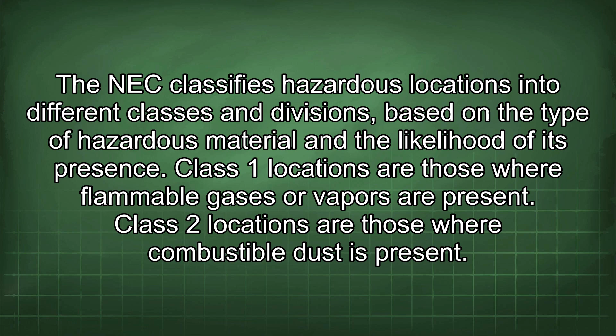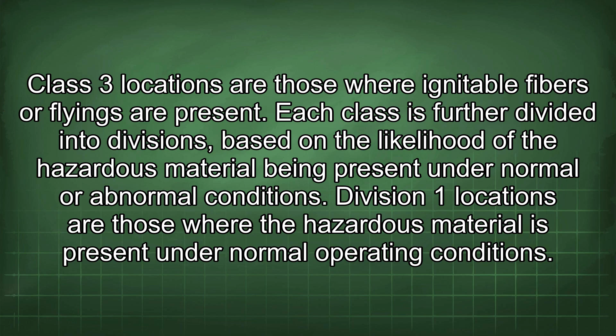Class 2 locations are those where combustible dust is present. Class 3 locations are those where ignitable fibers or flyings are present. Each class is further divided into divisions based on the likelihood of the hazardous material being present under normal or abnormal conditions. Division 1 locations are those where the hazardous material is present under normal operating conditions. Division 2 locations are those where the hazardous material is present only under abnormal conditions, such as a spill or equipment failure.